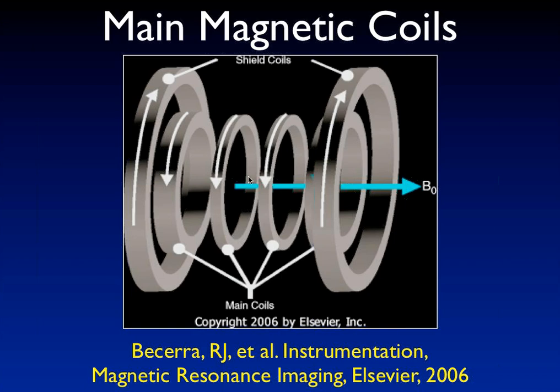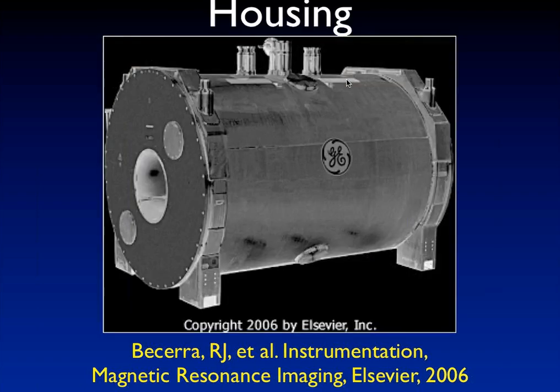This is a schematic diagram of roughly what the coils look like inside a typical modern superconducting magnet. You have solenoid coils in the center where the electricity flows in one direction. At the ends of the magnet, you have coils where the flow is in the opposite direction — these are shielding coils. This decreases the peripheral magnetic field extending into the room and is why these are called self-shielded magnets. All modern superconducting magnets are self-shielded.